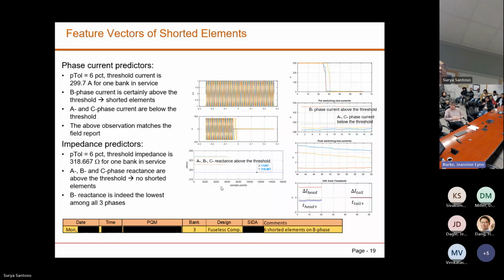So what does it mean? Are there shorted elements, do you think? There are no shorted elements - if there were shorted elements, the impedance should be below the threshold. So it means here there are no shorted elements. But what does the field report tell us? It tells us there are 6 shorted elements on B phase, on this phase. So it means they don't match. So my predictor may not be as good - this impedance predictor. That's quite perplexing, isn't it?